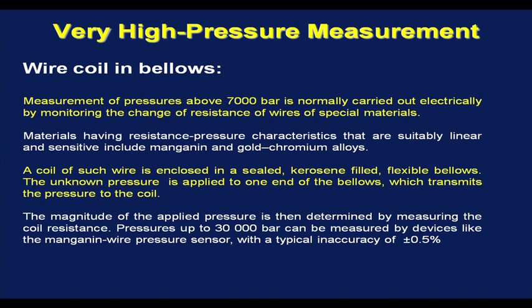After talking about pressure measuring instruments that are used for measurement of moderate pressure, let us now talk about how we can measure very high pressure. We are talking about pressures as high as 7000 bar. We can use an instrument called wire coil in bellows. Measurement of pressures above 7000 bar is normally carried out electrically by monitoring the change of resistance of wires of special materials.